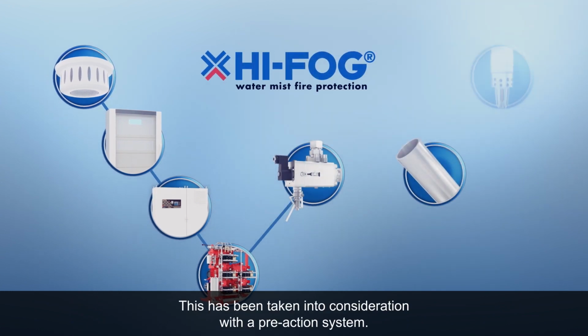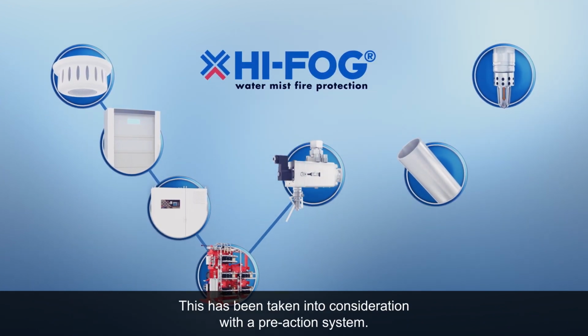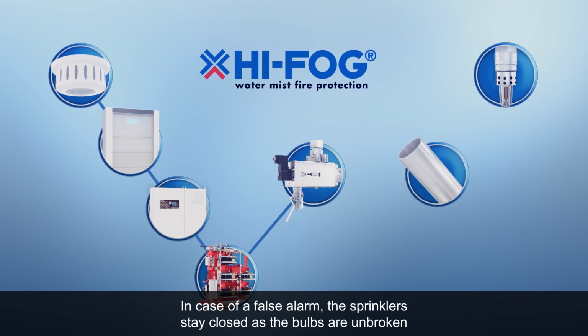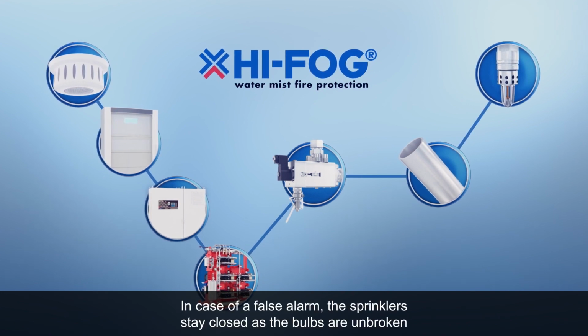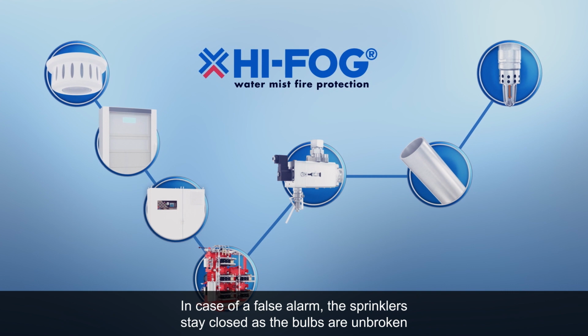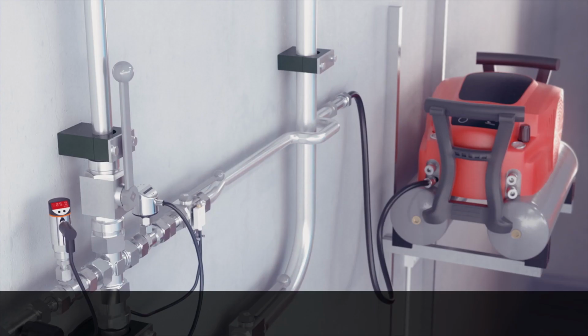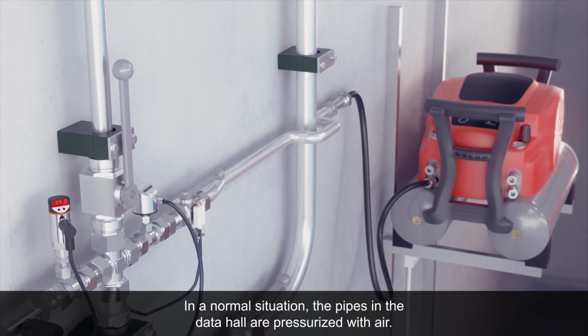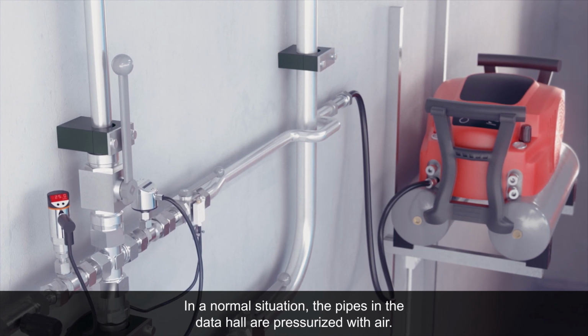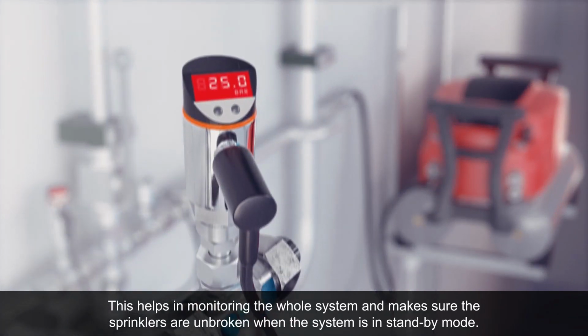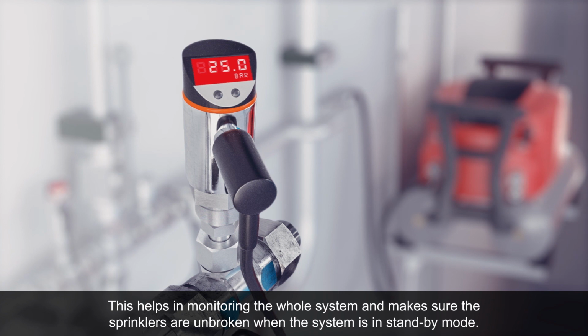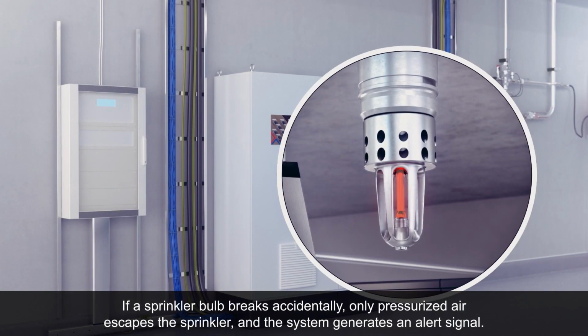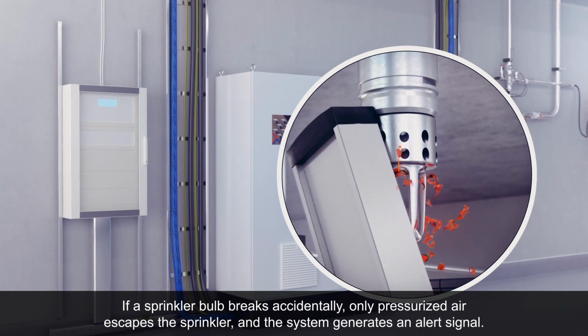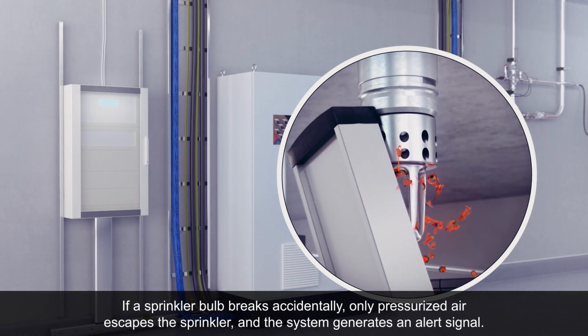Data center operators want to prevent false discharges in their data halls at all costs. This has been taken into consideration with the pre-action system. In case of a false alarm, the sprinklers stay closed as the bulbs are unbroken. In a normal situation, the pipes in the data hall are pressurized with air. This helps in monitoring the whole system and makes sure the sprinklers are unbroken when the system is in standby mode. If a sprinkler bulb breaks accidentally, only pressurized air escapes the sprinkler, and the system generates an alert signal.